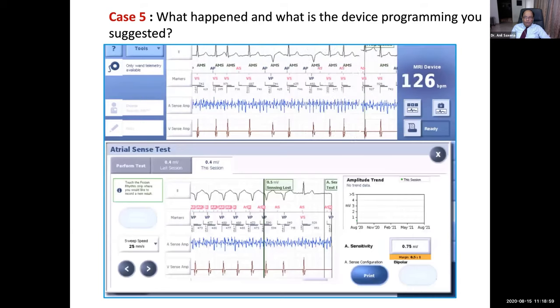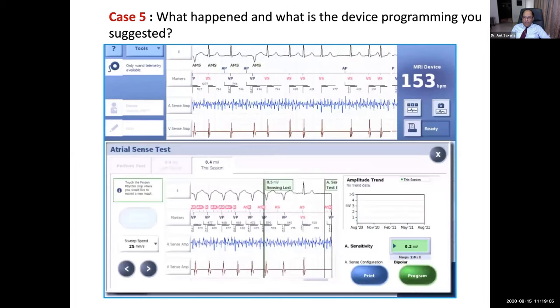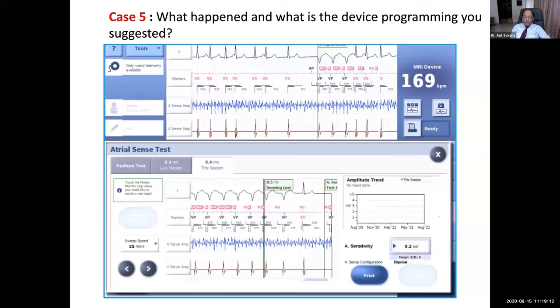So at 0.5, the sensitivity sensing was lost, so it was 0.4. We changed this to 0.2 and programmed it, and that's how it works. So programming is complete and the patient will then have proper sensing and automatic mode switch.